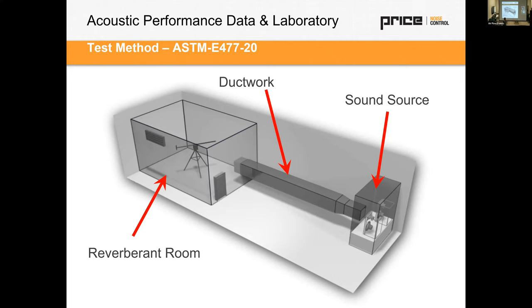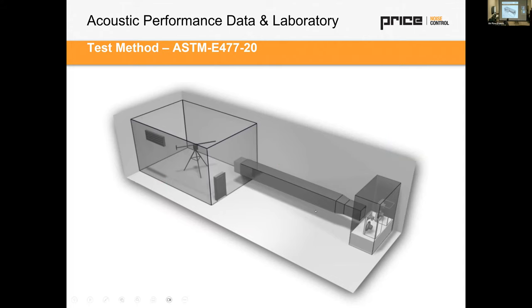We're actually going to look at this live in the lab, but the mock-up here helps to explain it quite easily. We typically start by generating noise and transmitting that through a series of different duct systems, different sizes, different shapes, to be able to mimic the silencer that we want to test. We then insert a silencer into that test setup, and we measure the noise reduction through that silencer. With and without that silencer in place is the reduction of sound, or insertion loss. When you measure the empty duct compared to that silenced system, you can get a feeling for how much sound removal there is.